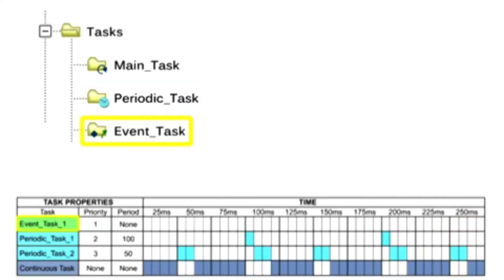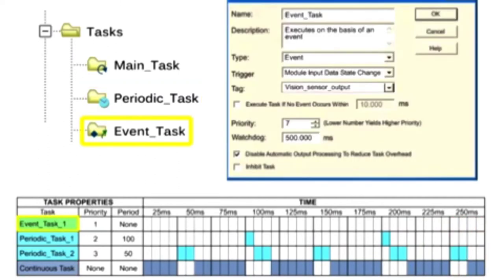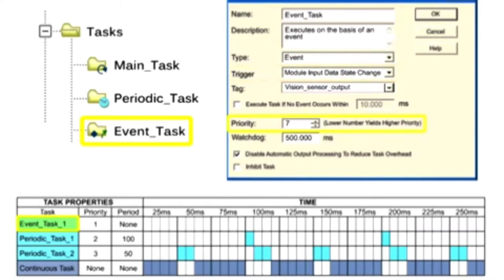Event tasks are executed immediately when a specific trigger occurs. A trigger is defined by the user and can be a change of state of an input or specific motion control operations. Event tasks are assigned priorities with the same scale of periodic tasks, ranging from 1 to 15.